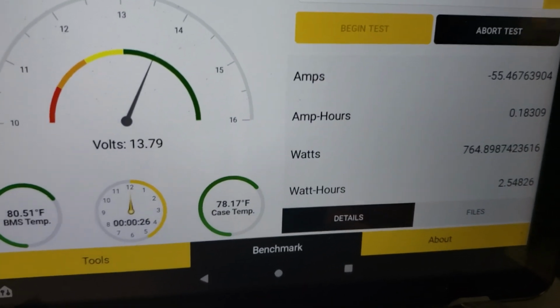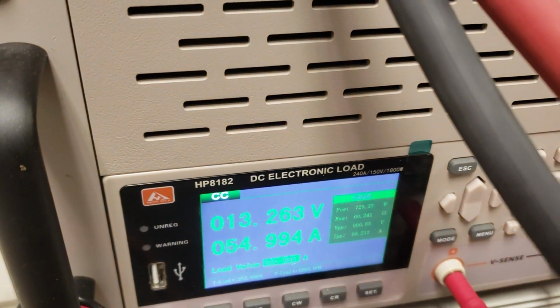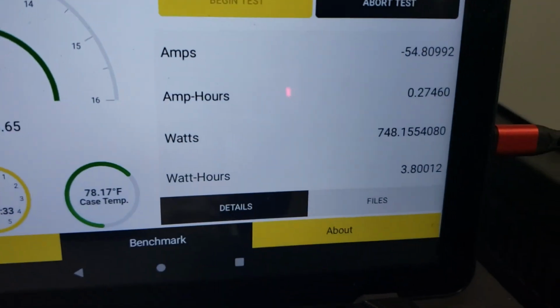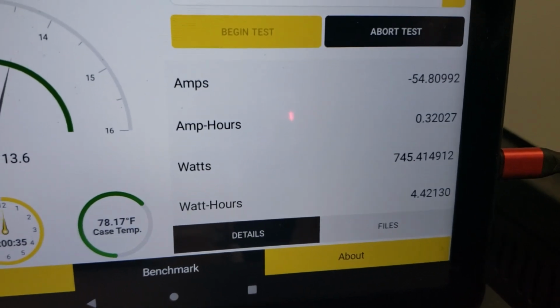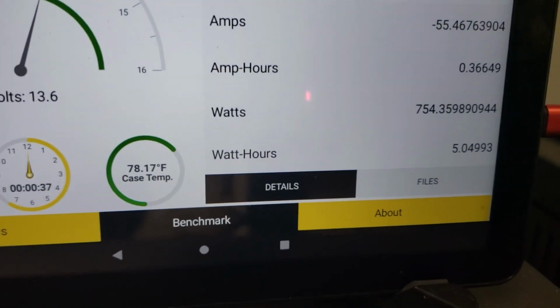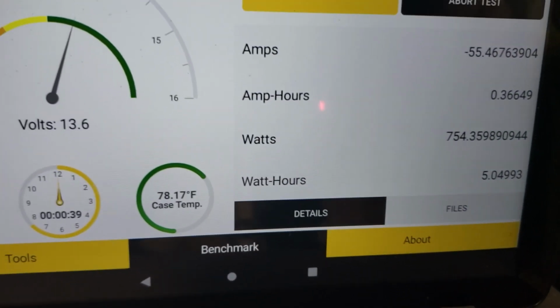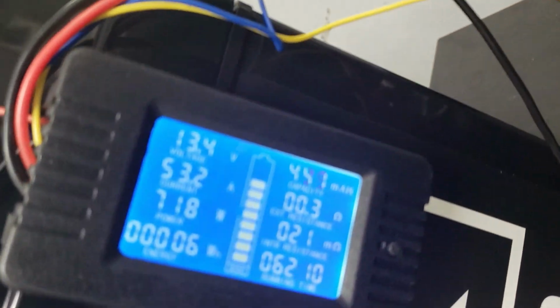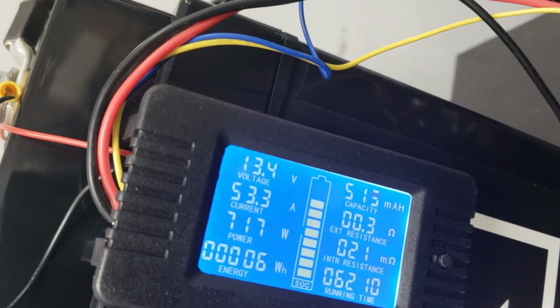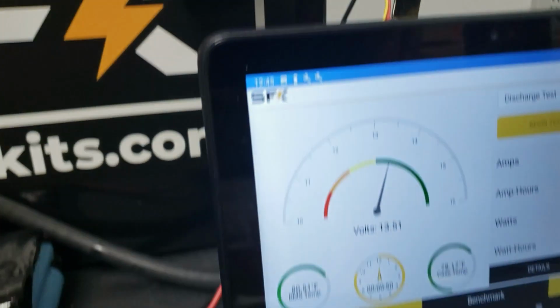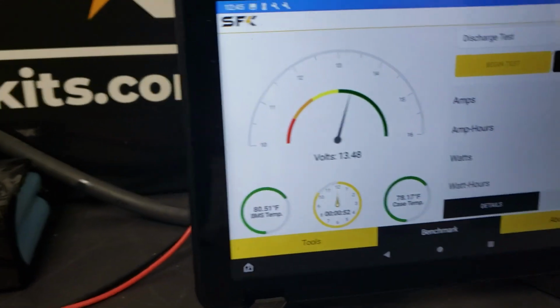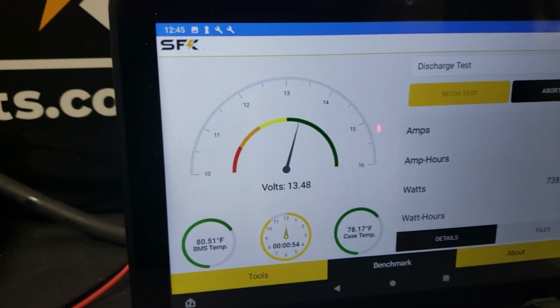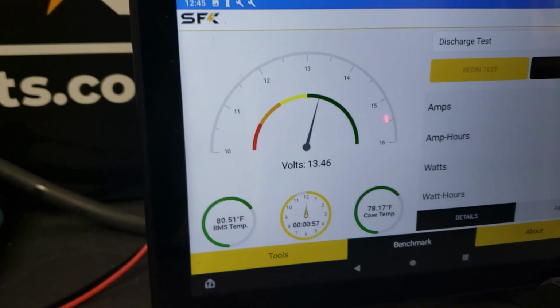As you can see, the electronic load is saying 54.994. The internal BMS shunt is saying 54. Well, now it's saying 55.46, and this shunt is saying 53.3. So right now we're comparing three different measuring things, and you can already tell there's like a 1 to 2 amp difference.